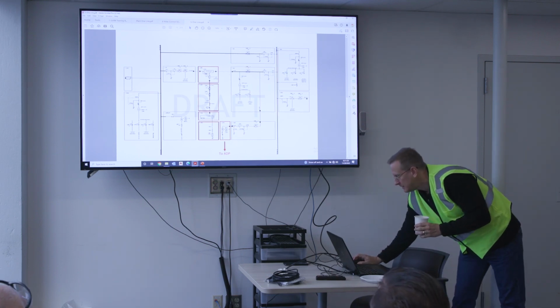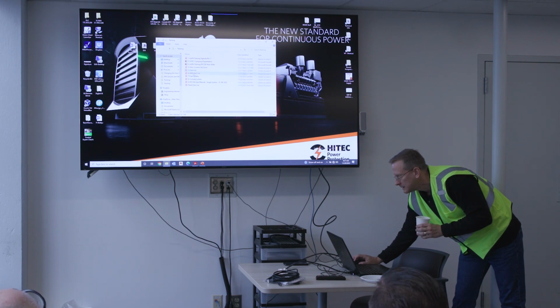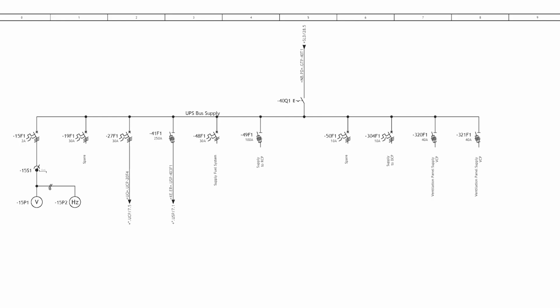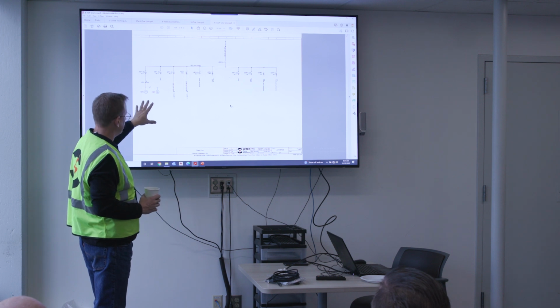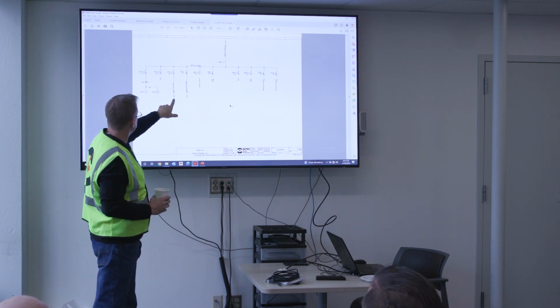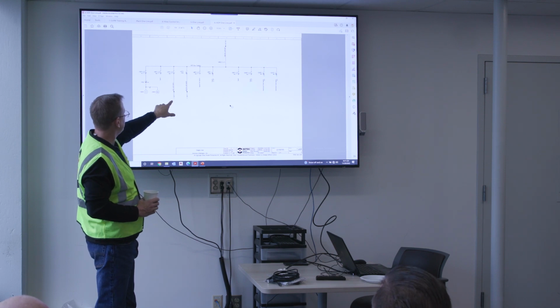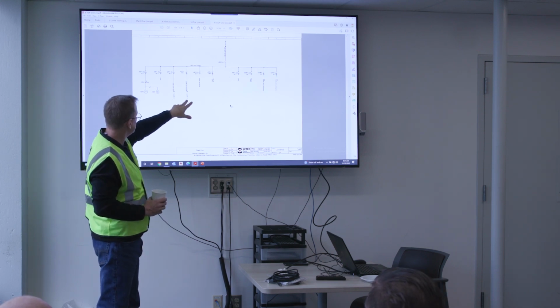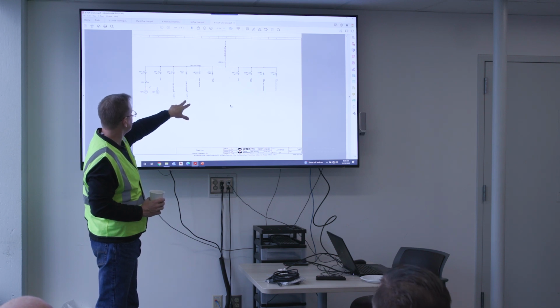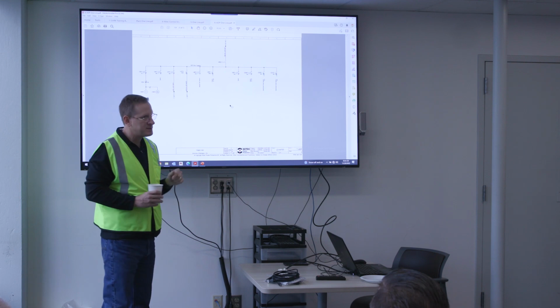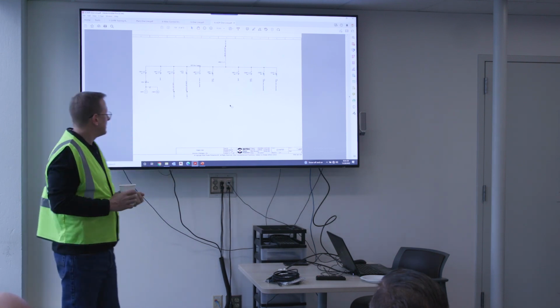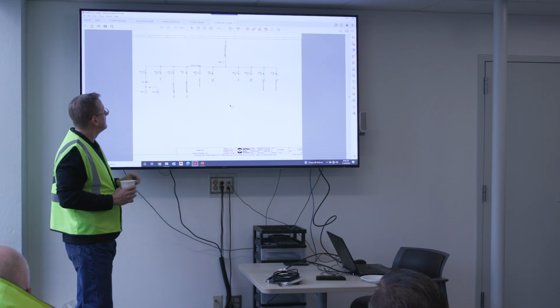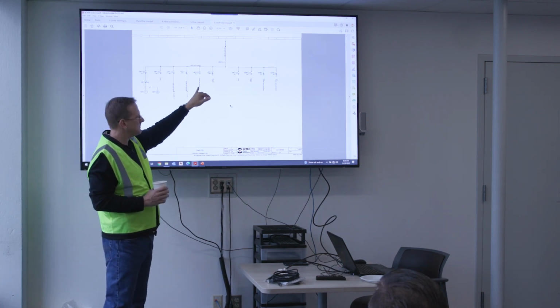And having said that, let me go to the ADP one line here. Okay, so this is a deeper look into our ADP. This is the GDP output, the low voltage three-phase 480 volt output of the GDP coming into our ADP. And so you can see some of the loads that the ADP provides for. This comes into the UPS for three-phase 480 for operating the UPS. Here's the UPS feed for 480 volts into the UPS. Here's a feed for the fuel system. We delivered a day tank with a day tank control panel that is basically fed from this feed here.